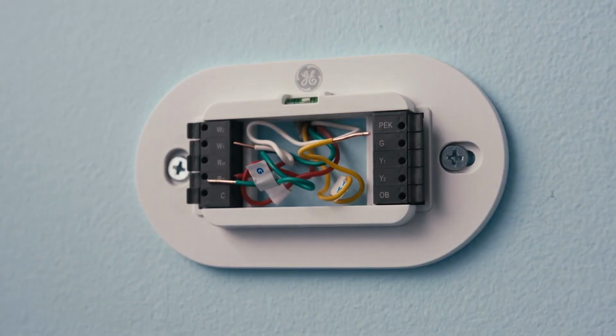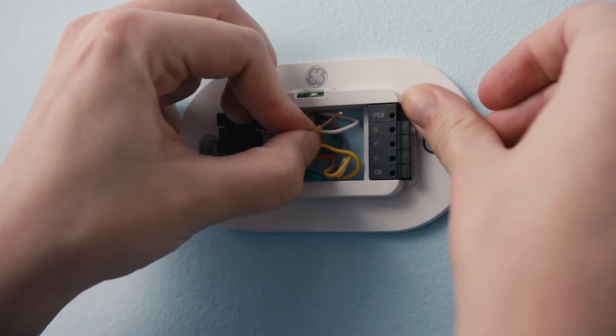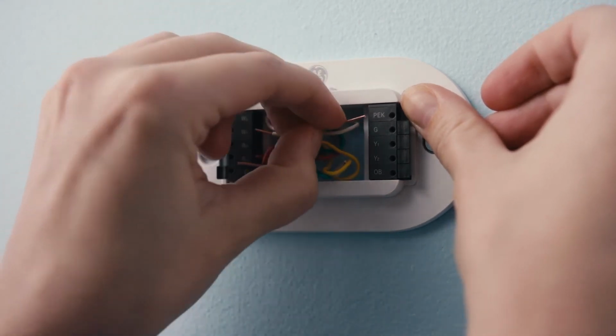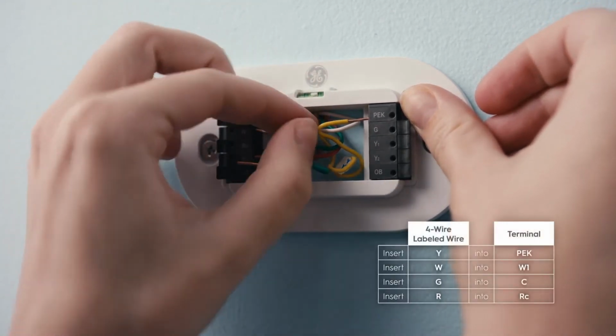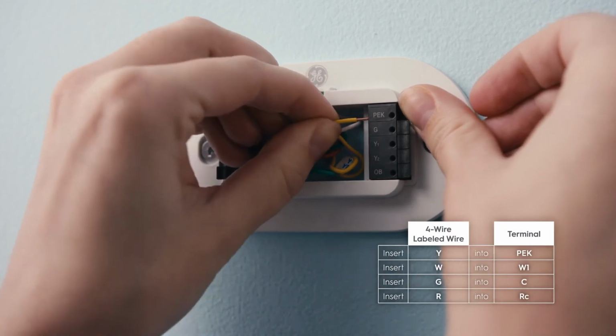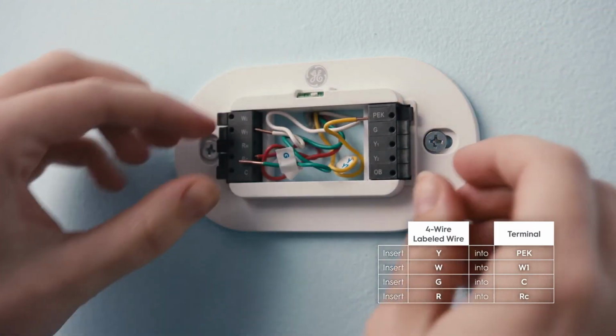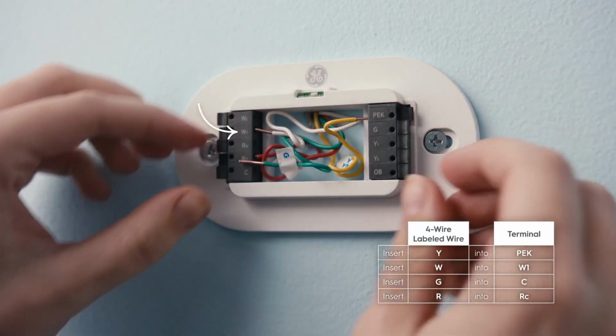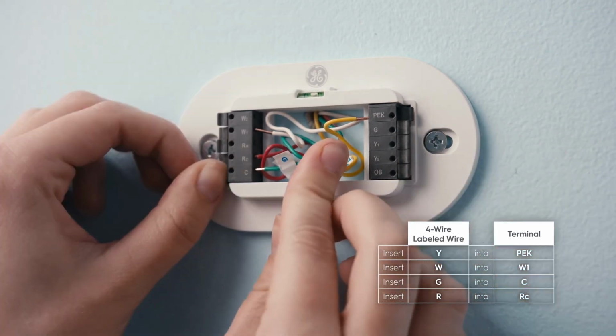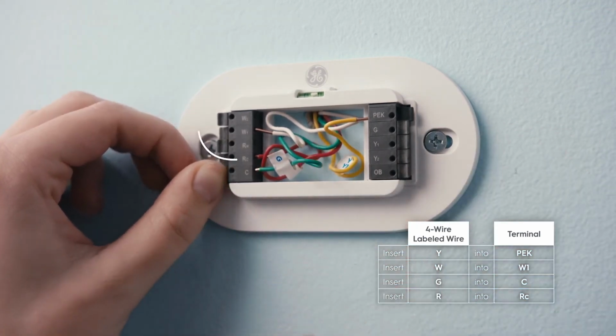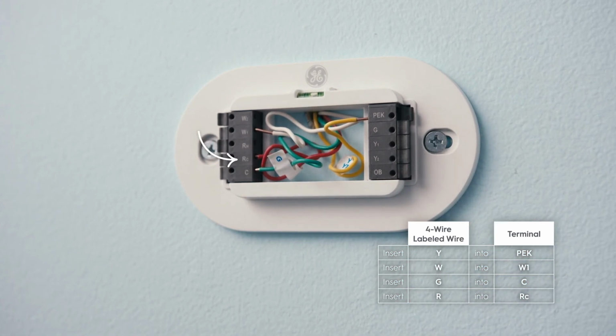Ready? Let's rewire the backplate terminals. Press the terminal lever on the side of the base plate. Slide the appropriately labeled wire into the correct terminal. When the wire is correctly inserted, the lever will stay depressed. For a 4-wire setup, wire Y or Y1 should go to terminal PEK. Wire W or W1 should go to terminal W1. Wire G to terminal C, and wire RC or RH to terminal RC.